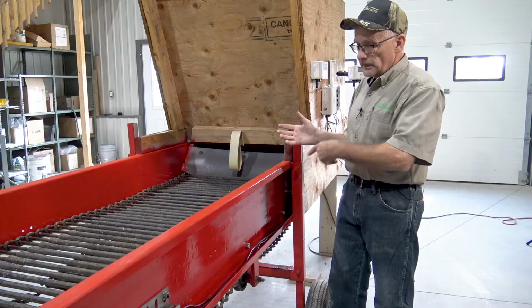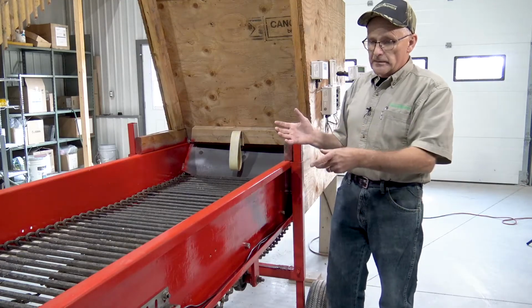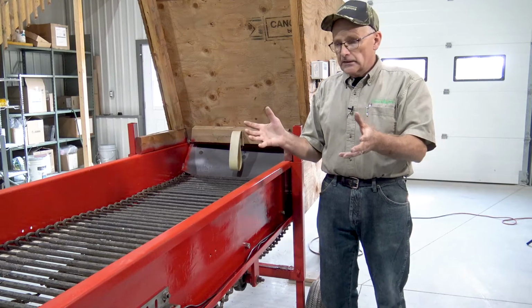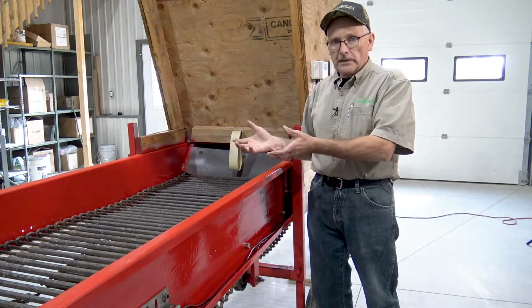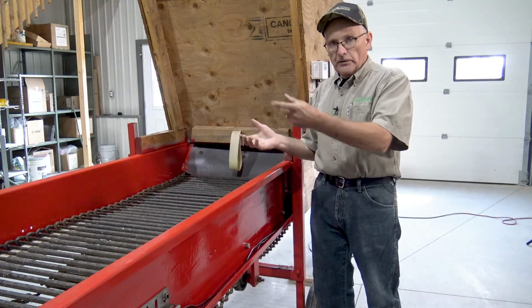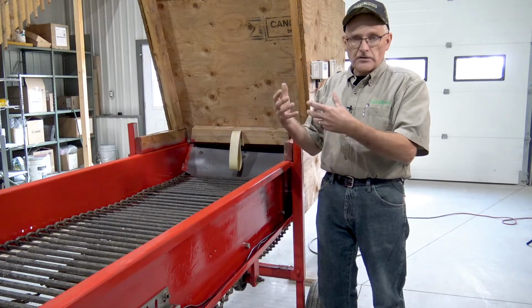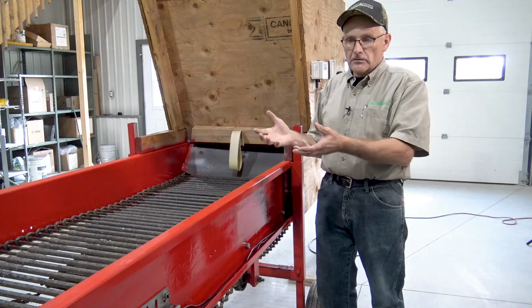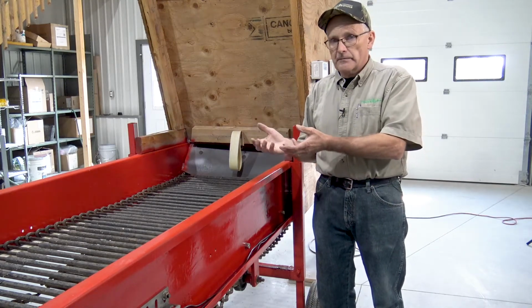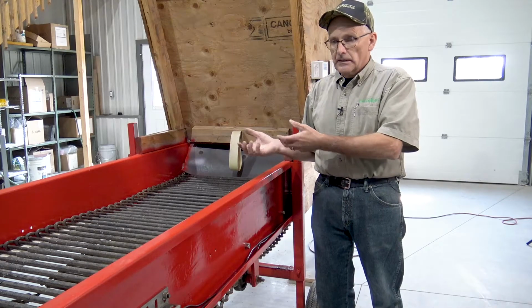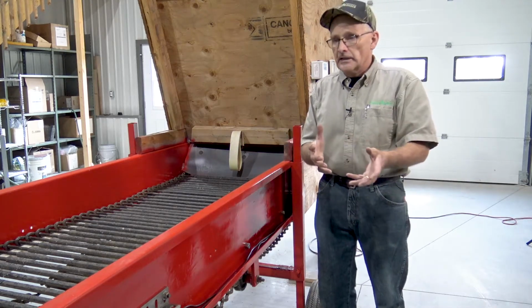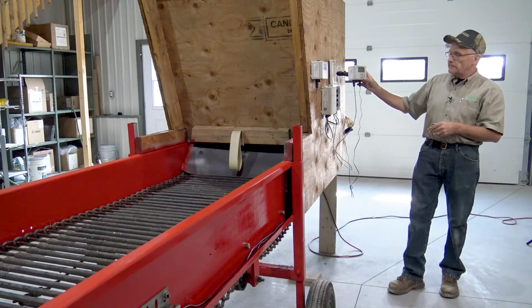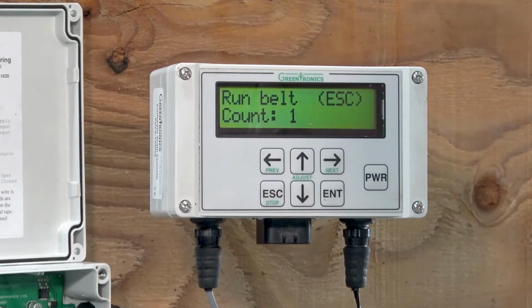The system will let the conveyor run around 3 times. It collects data about the weight of the empty belt when it's running for 3 whole revolutions, and it stores that information so that it knows what the zero weight of the empty conveyor actually is. And then it can automatically subtract that once we have weight running over it. So go ahead, Andy. Good, so we've started it.